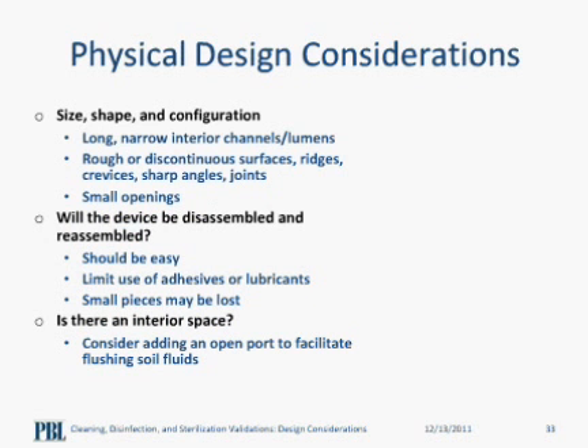Let's move to the physical design. In physical design consideration, manufacturers and engineers should establish that the size, shape, and configuration will not impose any constraints on the ability to clean, disinfect, and sterilize these devices. It poses a challenge to any healthcare personnel assigned to perform the cleaning process if they are confronted with the following design features, such as long, narrow internal channels with small openings, and devices with multiple internal channels. These are considered very challenging because they are not freely accessible. These are the areas that are difficult to reach when cleaning is performed.